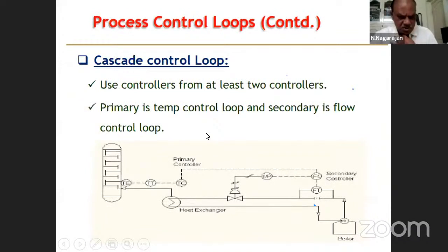Cascade control is when you have two variables being controlled, and they are cascaded to control the final control element. Here there is a distillation column where temperature is measured, and that temperature measurement is fed to the flow control of the steam. The temperature measurement is not directly going into the control valve; it goes to the flow measurement device. You take the measurement of the flow, and you have a flow controller. Here, similarly, you have a temperature controller. These two controllers are linked, and they decide the control action, which acts on the final control valve. This is called cascade control, because you are measuring two variables and using them to take one control action.